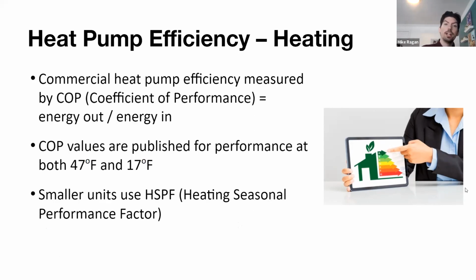Now, in heating, we have similar metrics that measure the performance of the system. One of these would be COP, coefficient of performance. Very similar metric. It analyzes the energy that you get out of the system divided by the energy that you need to put into the system. So, for example, if you're thinking of electric resistance heat, that's your baseboard with an electric resistance coil running through it. That's effectively a COP of 1. Actually, it's a little bit less than 1 because you're going to get some losses in that system. So it's about a 0.98 COP.